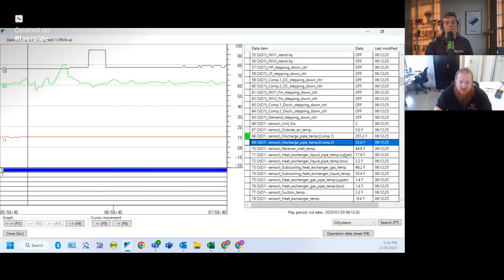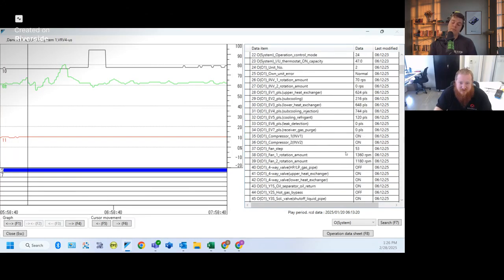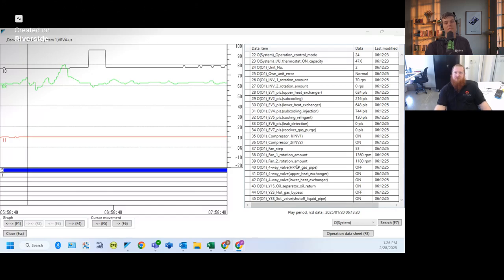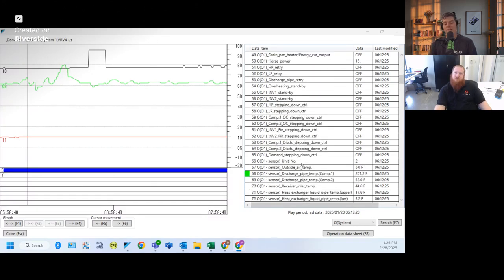And the way you can also confirm that is if you populate it, you can scroll from front to back on the system, and if there are no dips or marks or ups or downs, you can just rule it out, right? If there's no change and it doesn't match ambient, there's the other one. Even with a crankcase heater, if it doesn't match ambient, it's probably just not there.